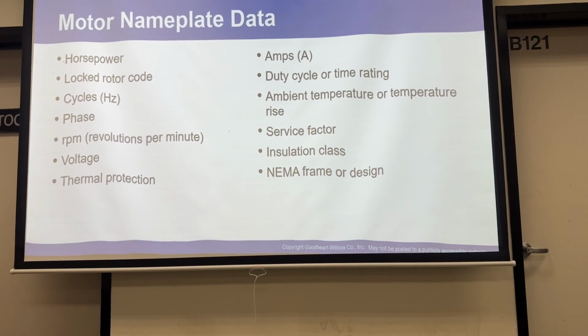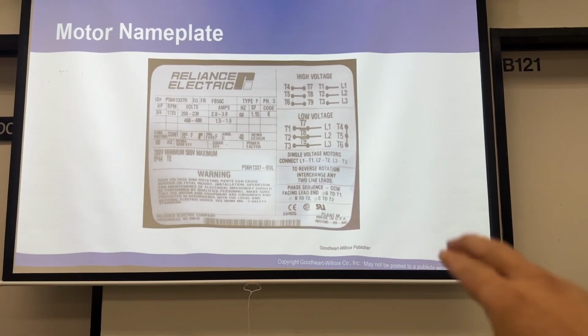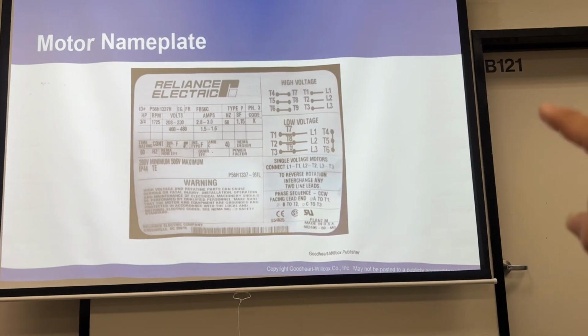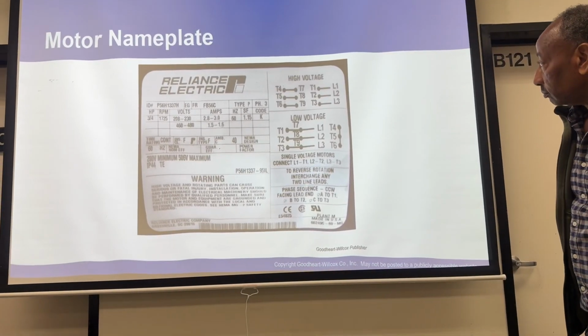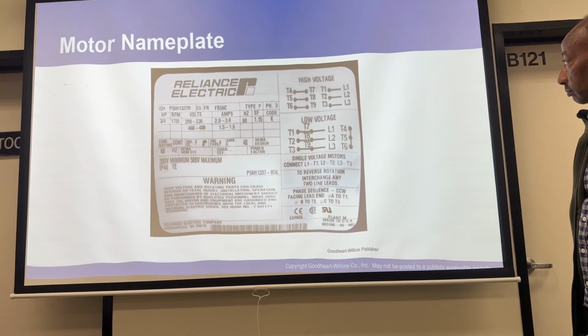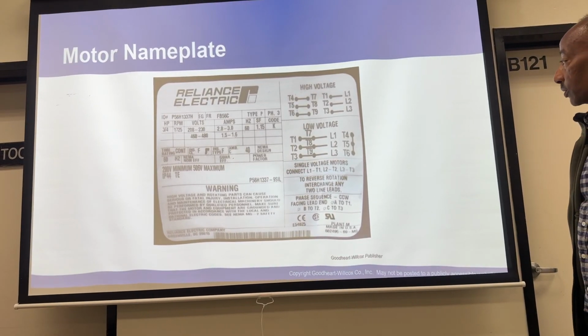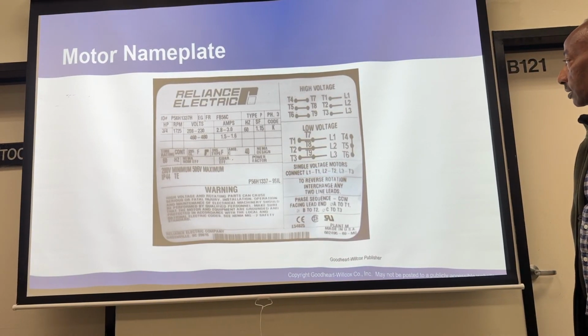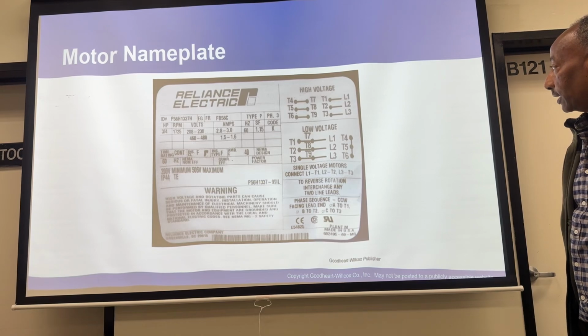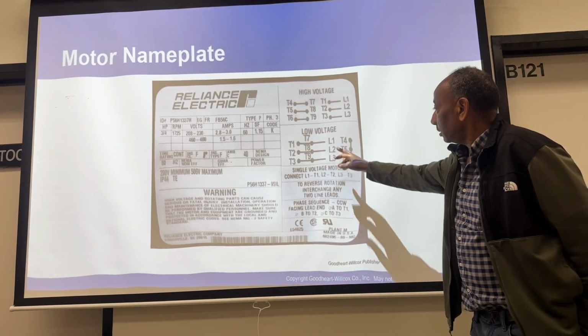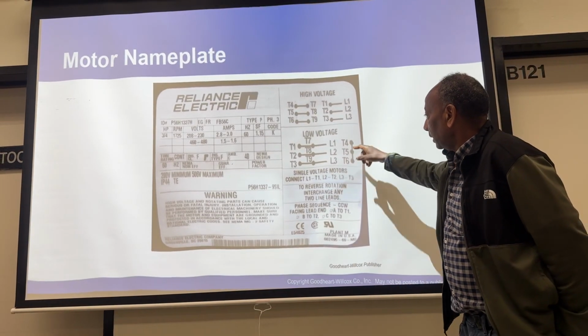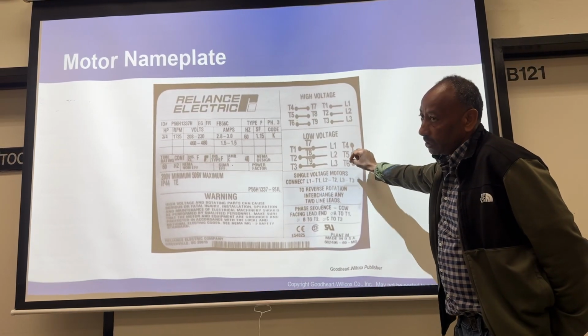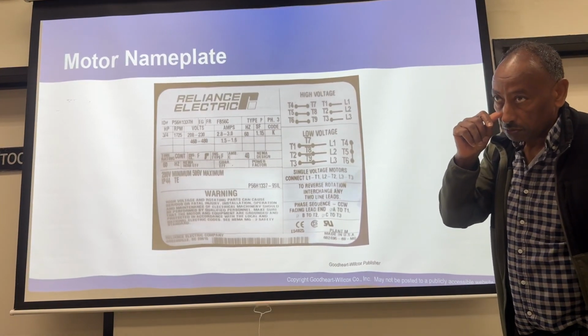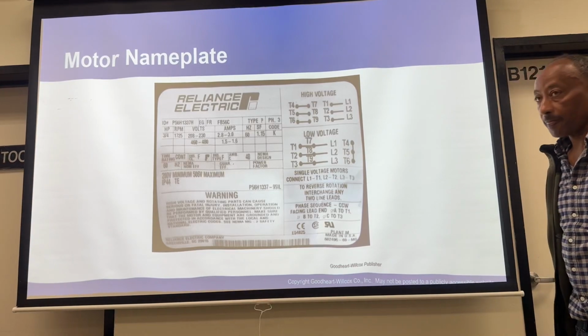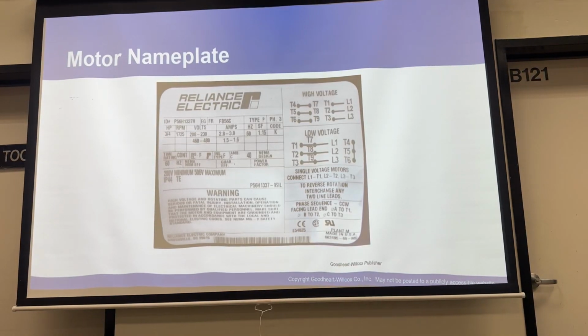Can you go back to that picture? On the low voltage side, when it says T4, T5, and T6, is that telling you to connect all of them together? Yeah — T1 and T7 together, T2 and T8 together, and T3 and T9 together. That's connected to L1, L2, and L3. And then these three wires are connected together too — that's in parallel. Low voltage is parallel, yes.